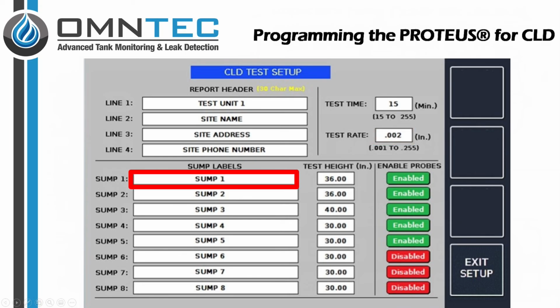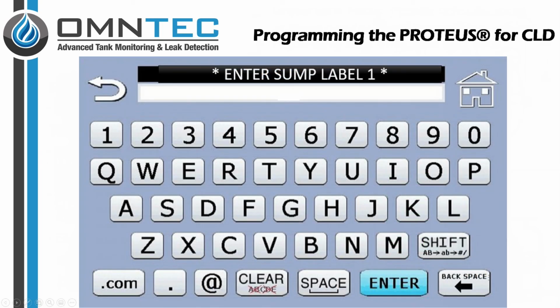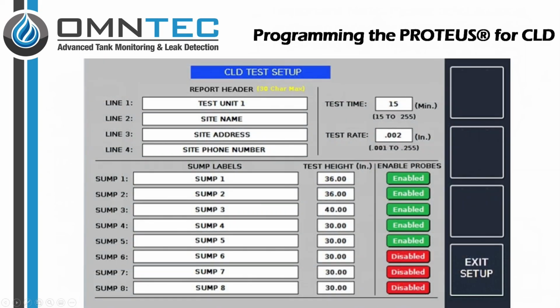Select a sump label to change the sump's name. Repeat for each sump or dispenser being tested. Use the keypad to enter the desired label. An example, regular sump or dispenser 1. Then, press enter. Enable any sumps that are being tested, otherwise disable that sump within the programming.